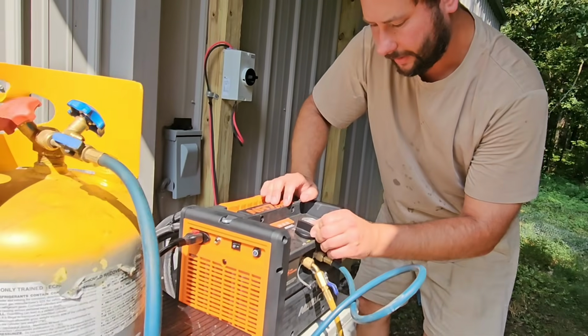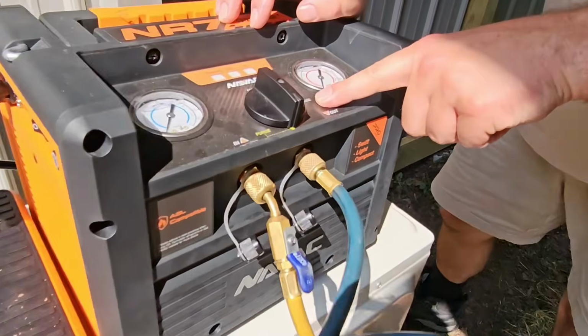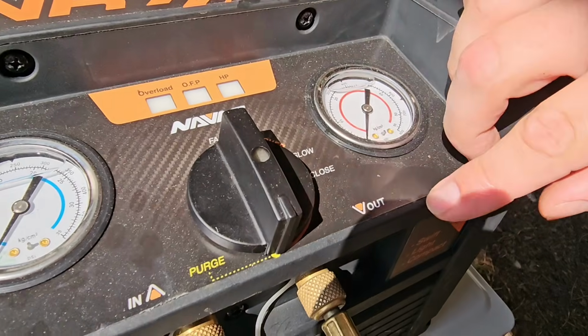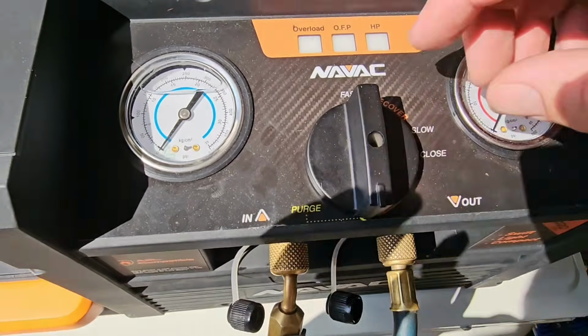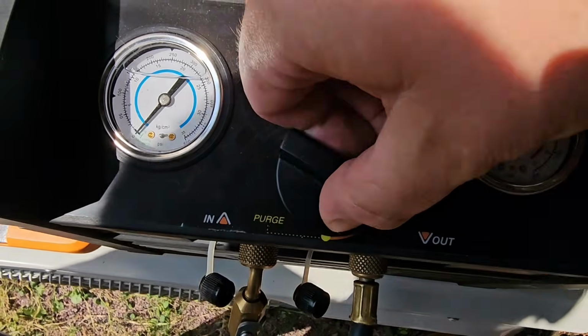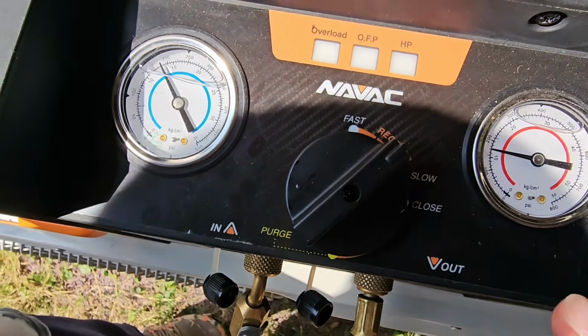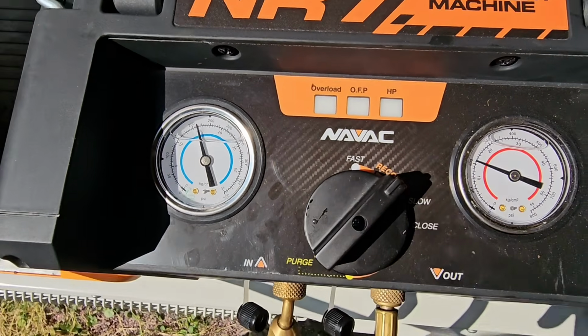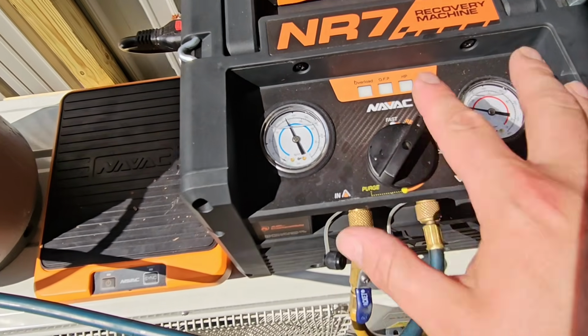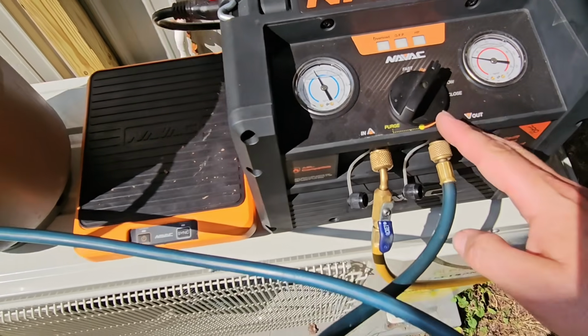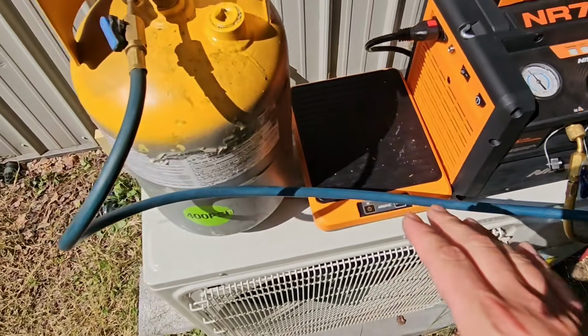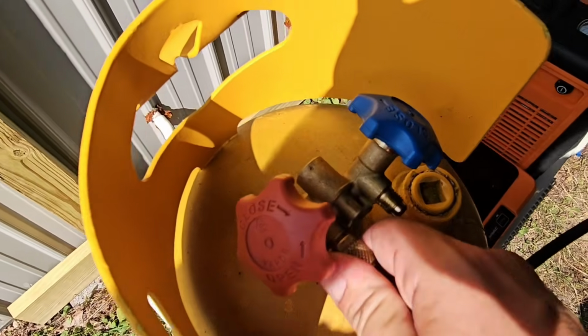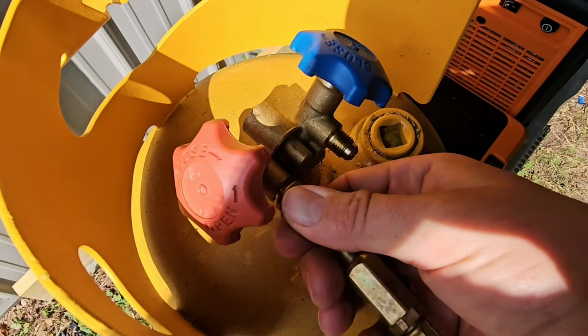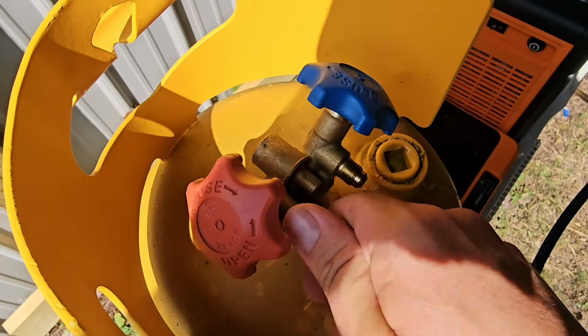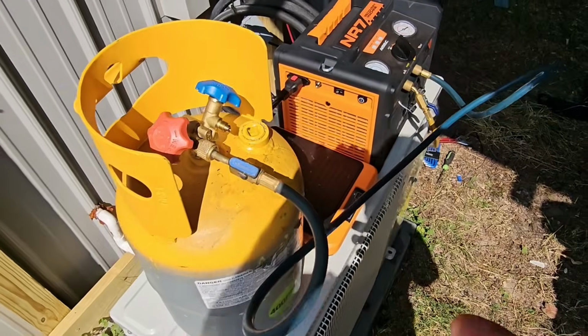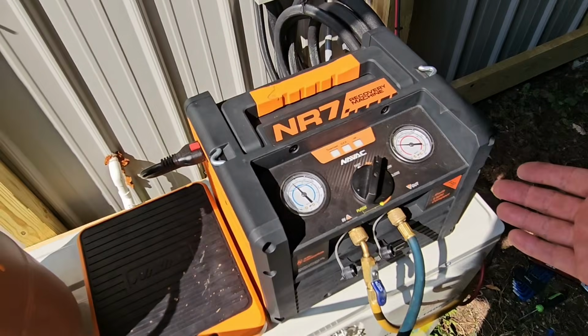Now we can turn this knob. Come over here. See this knob? This dial handles the purging and the recovering. You're going to turn this dial to where it says recover. They've got slow and fast because you can actually adjust the speed that this recovery machine recovers the refrigerant. So you can see our hoses are now filled with refrigerant, and what I like to do is bleed the hose at the tank. I just want to bleed that air out of the line because we're not wanting to recover air, we're wanting to recover refrigerant, right?